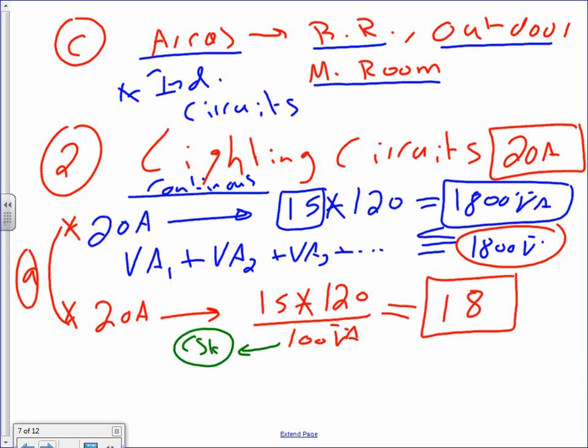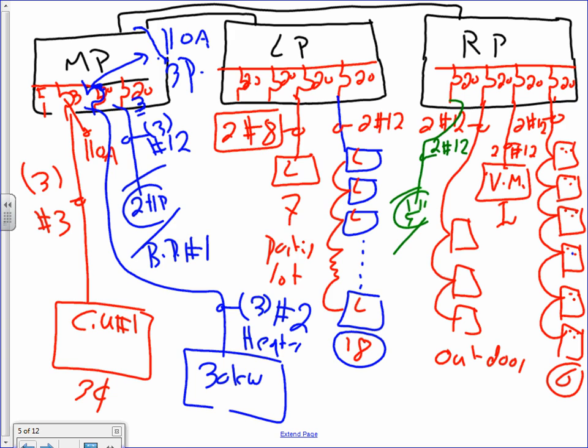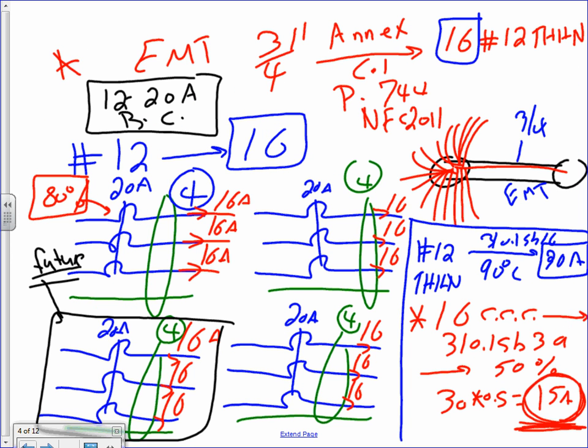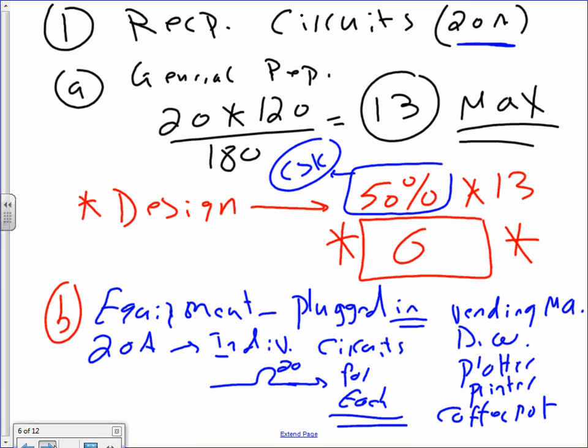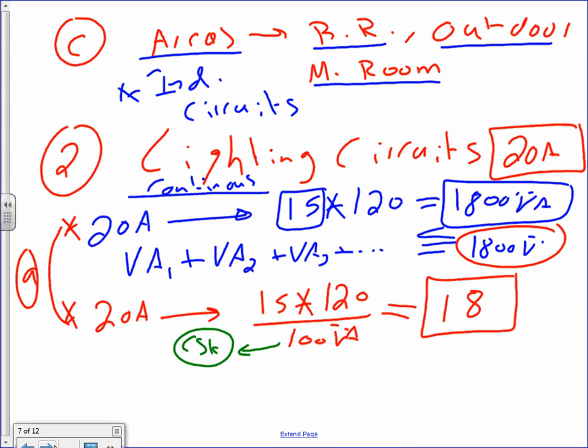Why not 16? Do you remember, guys, when we grouped them? When we grouped them and did the calculation based on grouping, you remember that 15 amp? I'm going to take into consideration that they're grouped, and I'm limited to 15 amps. Can I have a thumbs up? We understand where the 15 amps came from? Cool. So that's where the 15 amps comes from, grouping them. Go all the way. Okay, here's my 15 amps. A 15 amp circuit can only pull 15 amps. Multiply by 120, gives you 1800 volt-amps.